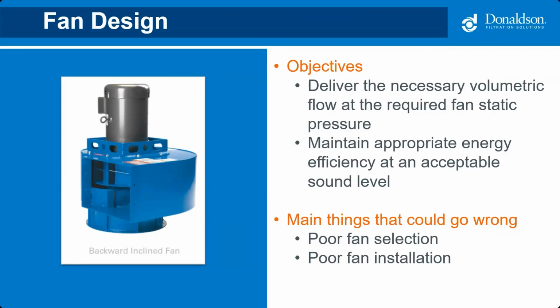Our fan is like the heart of the local exhaust system. It has 2 job responsibilities. First, it has to deliver the necessary flow at the required static pressure to drive the operation of the system. And since many dust collectors can operate with clean or dirty filters, the required airflow often has to be maintained over a range of static pressures. Secondly, the fan you select should be able to maintain the appropriate energy efficiency at an acceptable sound level. For example, non-material handling fans located on the clean side of a collector are more efficient than material handling fans on the dirty side of the collector.